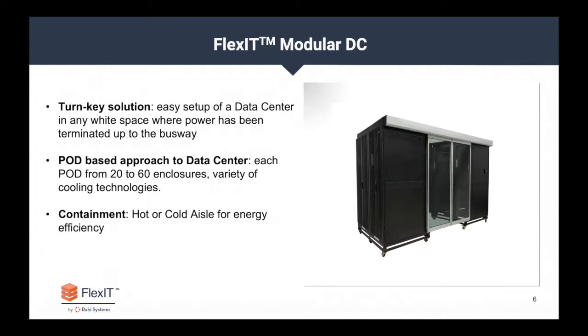The modular data center is really designed to be deployed in an existing data center white space, such as a co-location environment where power has been terminated up to the busway, and cooling solutions have been implemented, such as CRAC or CRAH units, blowing air from either underneath the raised floor or from up above.